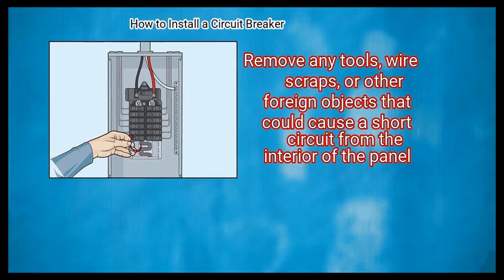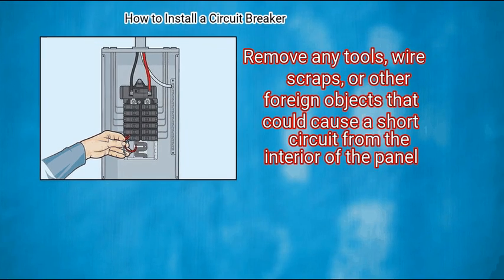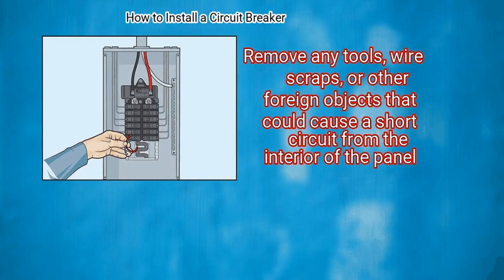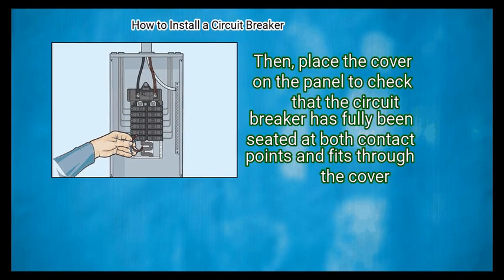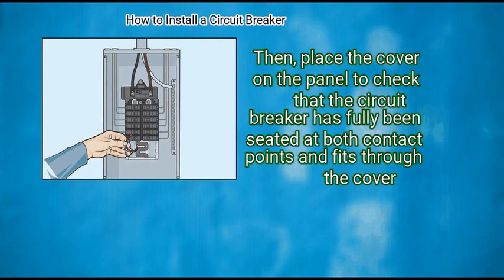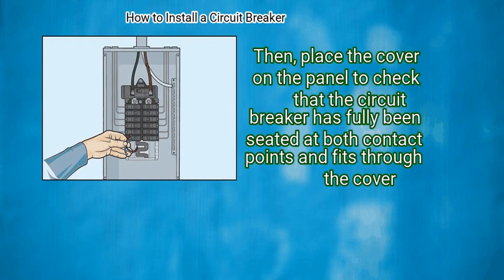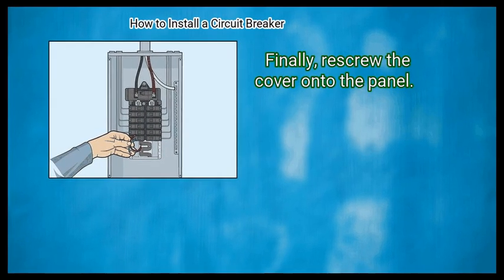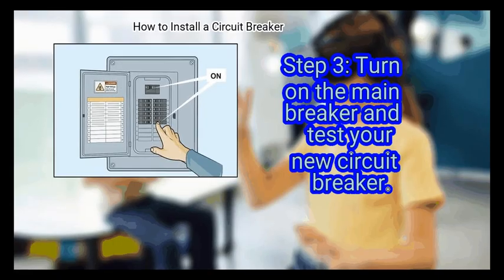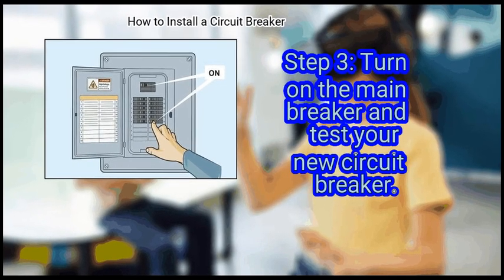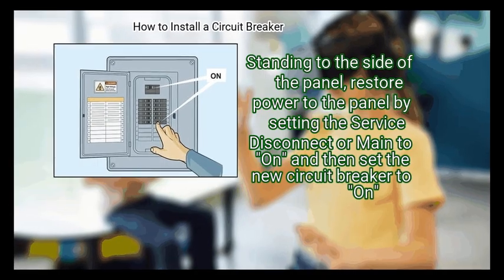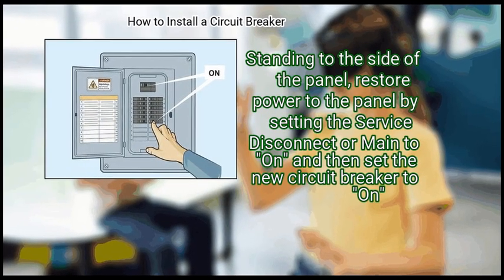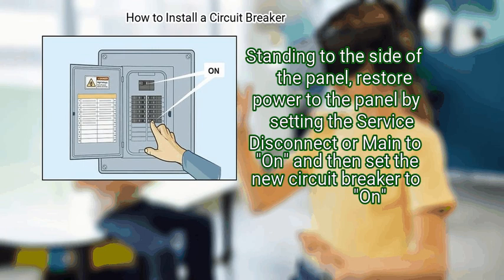Remove any tools, wire scraps, or other foreign objects that could cause a short circuit from the interior of the panel. Then, place the cover on the panel to check that the circuit breaker has fully been seated at both contact points and fits through the cover. Finally, rescrew the cover onto the panel. Step 3. Turn on the main breaker and test your new circuit breaker. Standing to the side of the panel, restore power to the panel by setting the service disconnect or main to on, and then set the new circuit breaker to on.